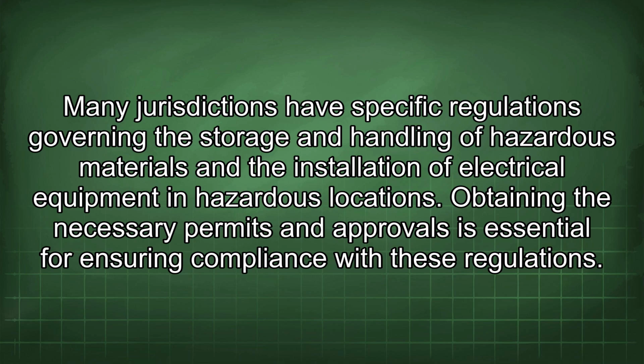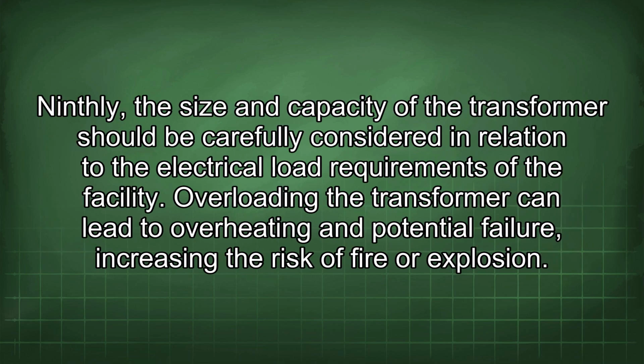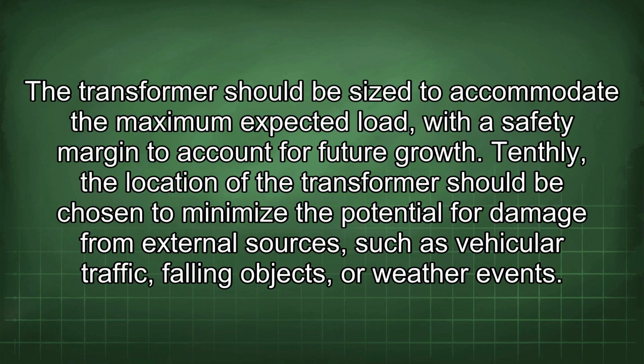Obtaining the necessary permits and approvals is essential for ensuring compliance with these regulations. Ninthly, the size and capacity of the transformer should be carefully considered in relation to the electrical load requirements of the facility. Overloading the transformer can lead to overheating and potential failure, increasing the risk of fire or explosion. The transformer should be sized to accommodate the maximum expected load, with a safety margin to account for future growth.